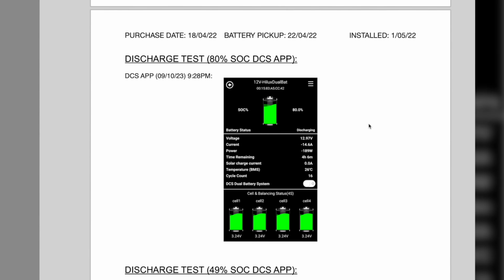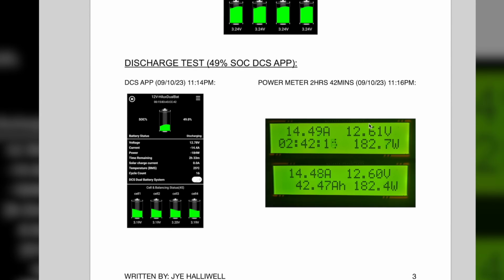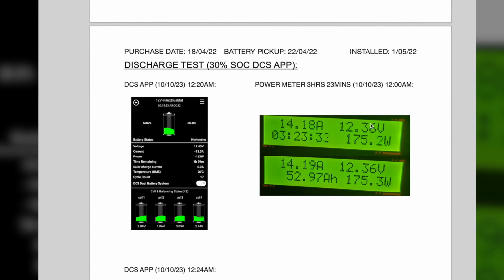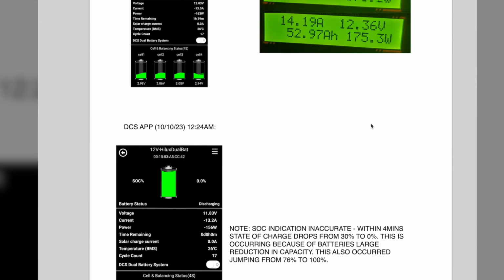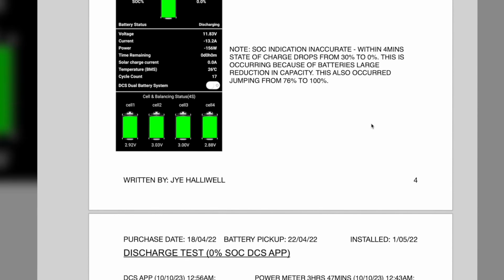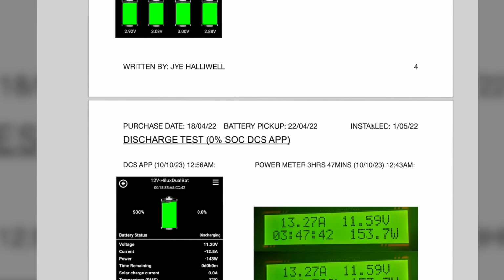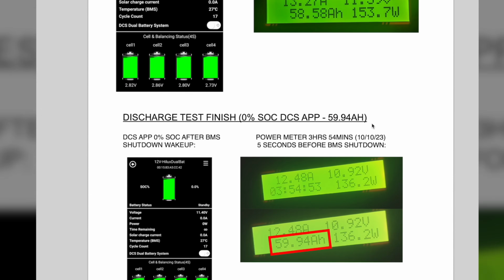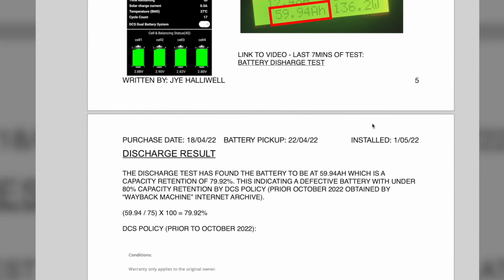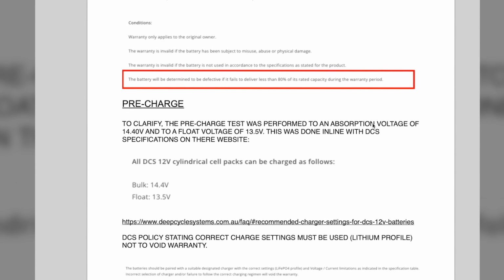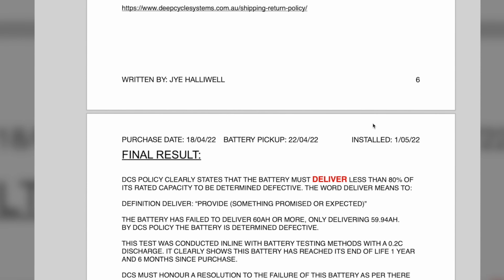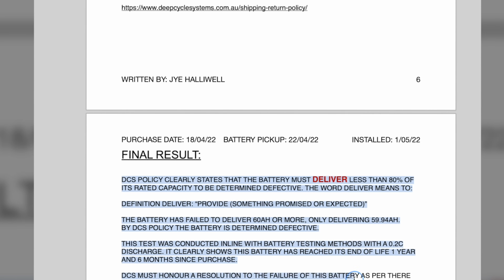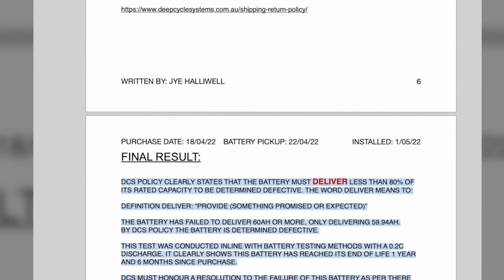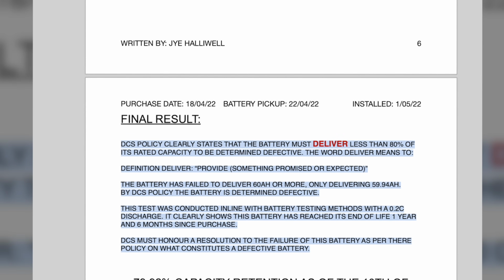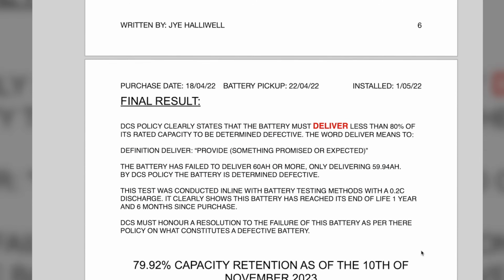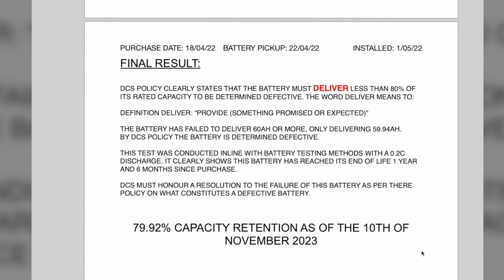DCS's response was unusual. They performed a capacity test by discharging the battery with 93 amps down to 11.39 volts — lower than their own specifications — and then recharged it to 14.7 volts using a custom Victron profile, higher than their guidelines. This method displayed just under 20% capacity loss. However, charge tests aren't reliable for assessing true battery capacity due to potential internal resistance issues, particularly if there are faults in the cell pack. A discharge test is generally more accurate.